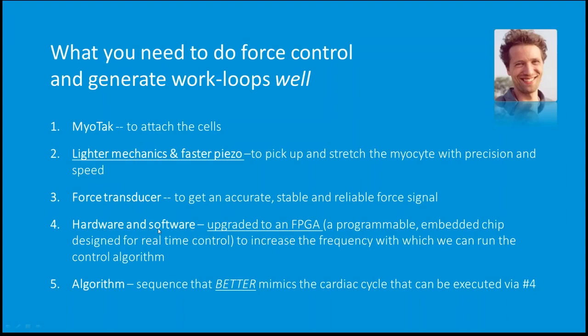For hardware and software, LabVIEW wasn't going to cut it. The maximum we could run the iteration loop at properly was a few hundred hertz, and that's just not fast enough. Instead, we started to use what's called an FPGA, an embedded chip that can take pretty complicated protocols but is designed for real-time control, so you can run the feedback loop at pretty much unlimited speed.